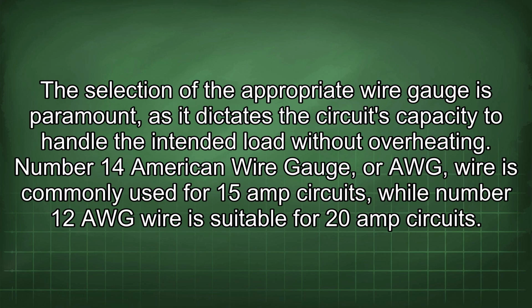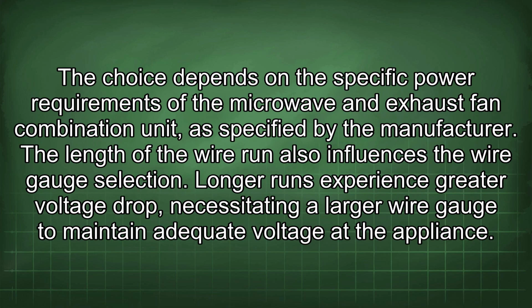The selection of the appropriate wire gauge is paramount, as it dictates the circuit's capacity to handle the intended load without overheating. Number 14 American wire gauge, or AWG, wire is commonly used for 15 amp circuits, while number 12 AWG wire is suitable for 20 amp circuits. The choice depends on the specific power requirements of the microwave and exhaust fan combination unit as specified by the manufacturer. The length of the wire run also influences the wire gauge selection.